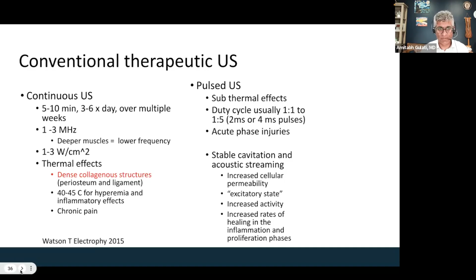Unlike a radiofrequency needle, which will have a thermal probe, there's no easy way to know the temperature you're getting in a patient. It might have some clinical effect. They might notice the temperature being hot in their skin, because this is an ultrasound probe being placed on the skin for multiple minutes of therapeutic modalities. So these are usually 10-minute settings, 15-minute settings, somewhere around there, and usually covering a few inches squared with your therapeutic ultrasound. So the treatments are 15 minutes, and you're hoping for a thermal effect or a mechanical effect. Next slide.